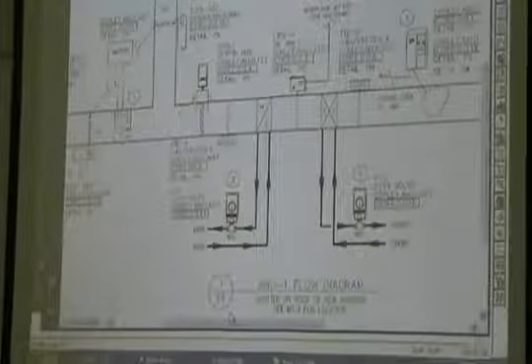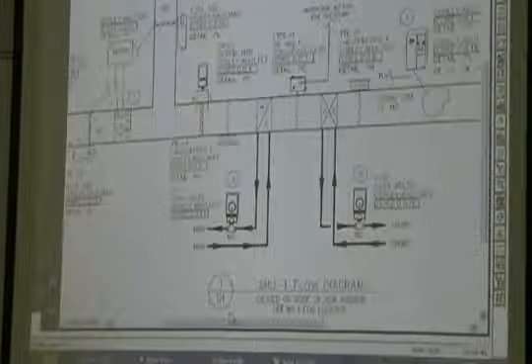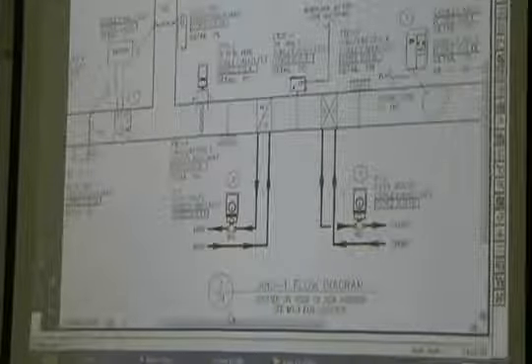Heating coil, heating valve, same thing. It's on the return side. These little symbols underneath here are just normally open, normally closed. Used to, in the pneumatic days, that was critical that you got those straight, because you might have just one signal going to both valves, and they had to sequence based on one being normally open, normally closed. With DDC, we can make them either way we want to. So that becomes a customer preference or an engineer's preference. Doesn't really matter to us in the DDC world whether it's normally open, normally closed.